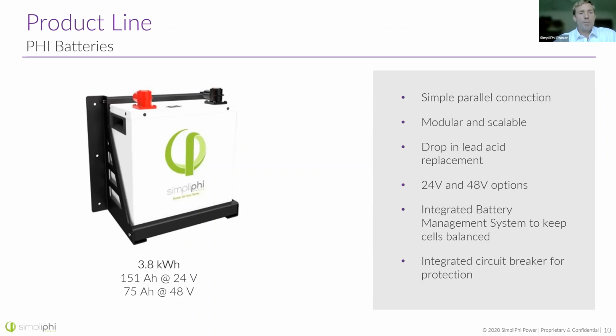So capacities for batteries are often specified either in kilowatt hours — power times time gives you energy — or in the number of amp hours the battery has, but then you have to keep in mind what the voltage is. Our Phi battery comes in 2 different voltages, 24 volt or 48 volt. The 24 volt and 48 volt batteries both have the same number of cells.